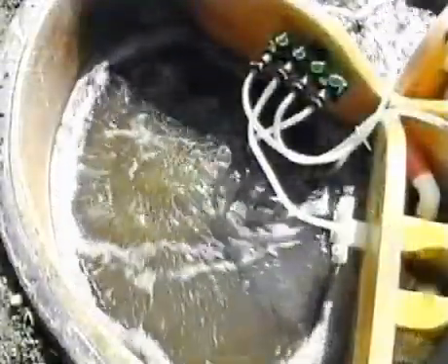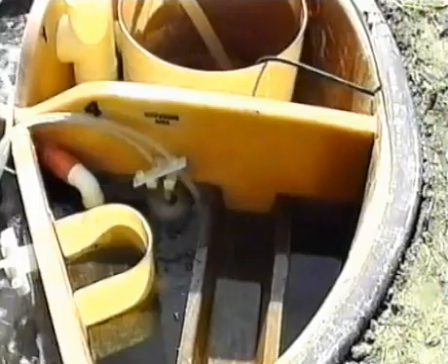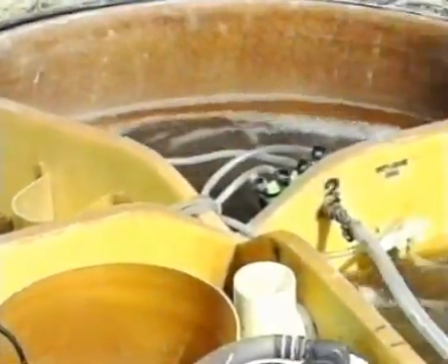A small diaphragm pump is used to produce the micro-bubbles needed for aeration and to mix the sludge. The aerated mixture, comprising biological sludge and purified water, moves on to the settler, which is the fourth chamber. The purified water can then be discharged into a body of water, and the excess sludge is recycled and returns to the oxidation chamber.